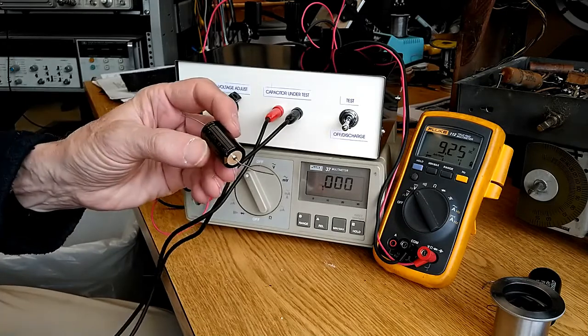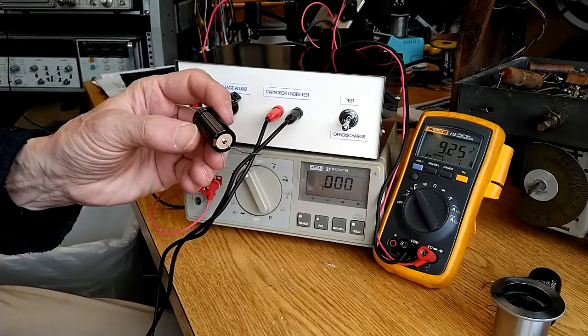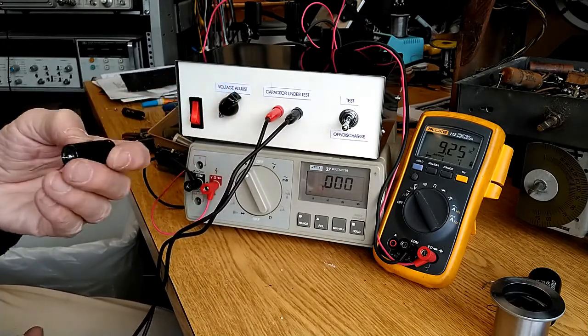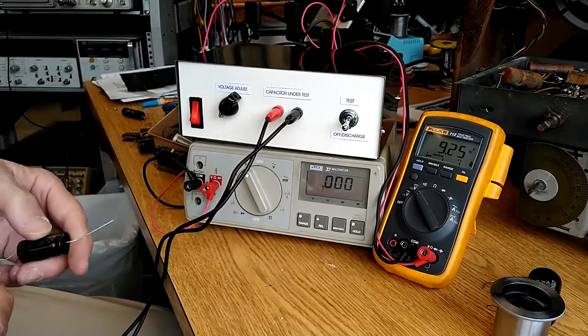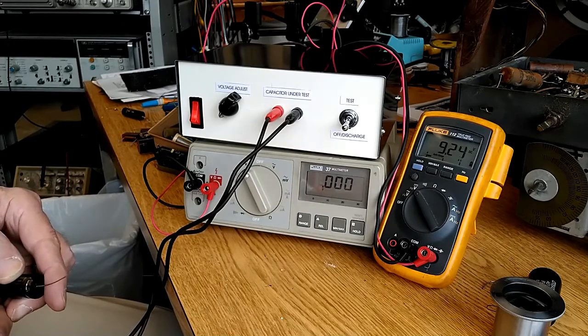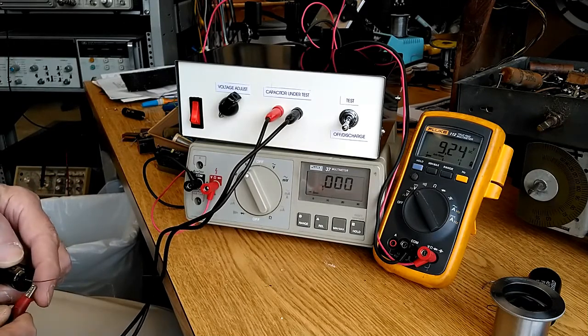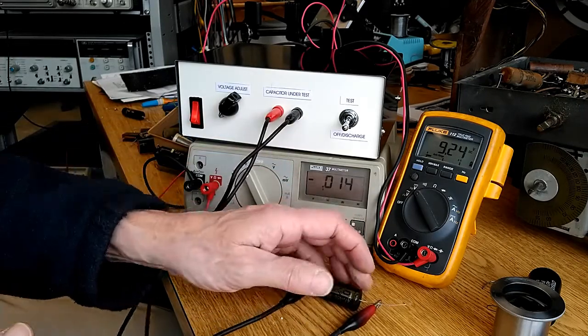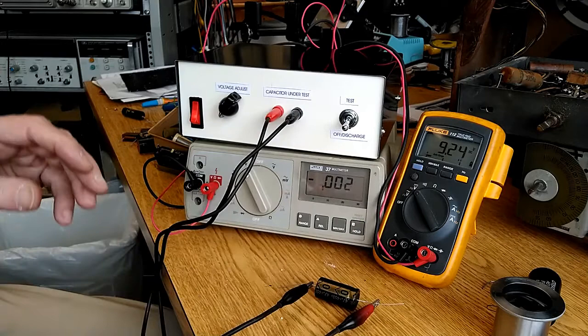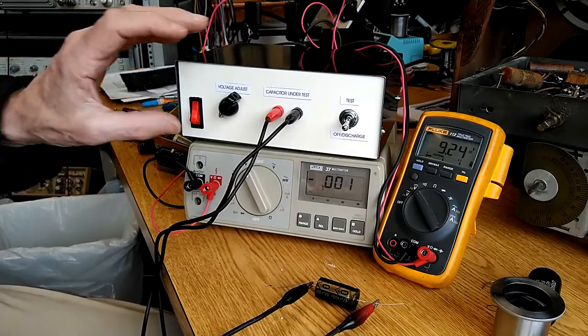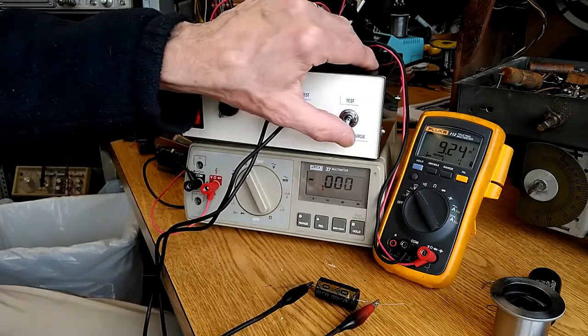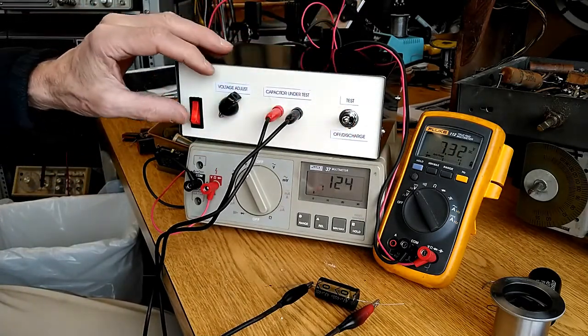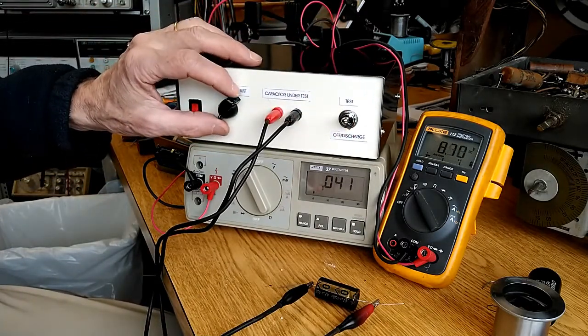Here's a newer capacitor, rated 47 mics at 450 volts. Put it in the test position, and increase the voltage.